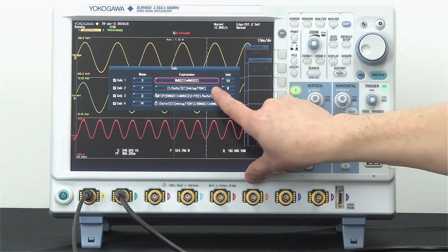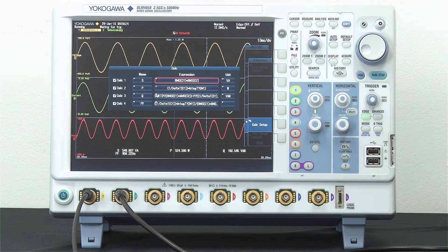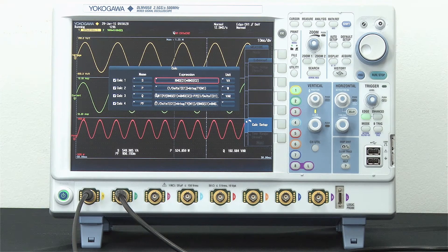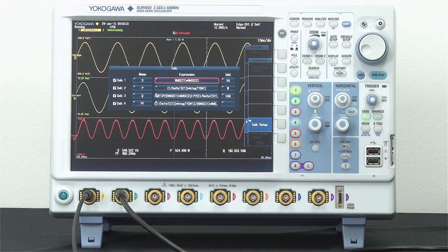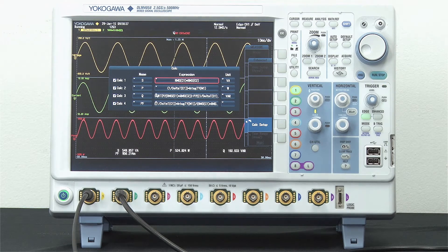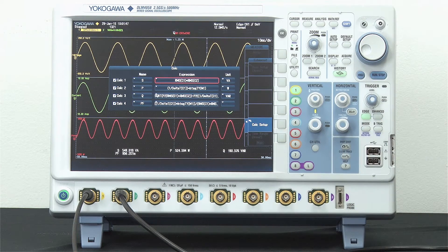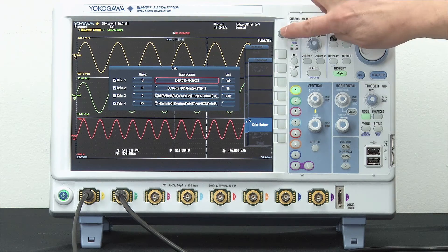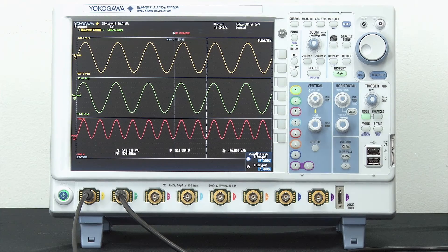Below calc one are three other equations. One for real power, one for reactive power, and a fourth equation for power factor. Each of these equations are IEEE standard or empirical equations for those parameters. As you can see, the onboard calculator can perform numeric integration. So right here you'll see an integral. So the equations have been properly entered at this point, and now I simply press the escape button a couple of times, and I just want to completely back out of the calculator menu. Then I press run.